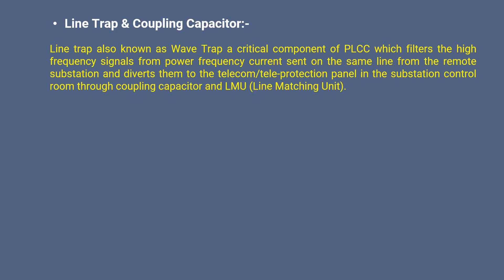Line trap, also known as wave trap, is a critical component of PLCC which filters the high frequency signals from power frequency current sent on the same line from the remote substation, and diverts them to the telecom and teleprotection panel in the substation control room through coupling capacitor and LMU (Line Matching Unit).